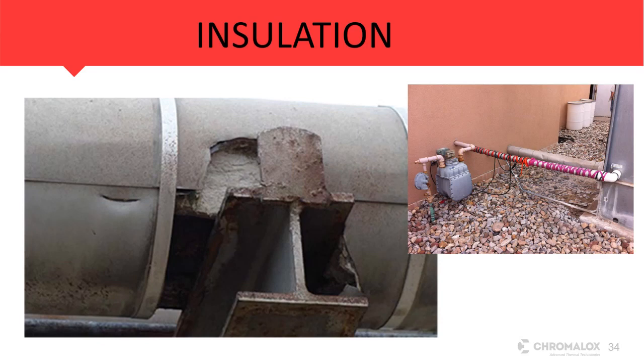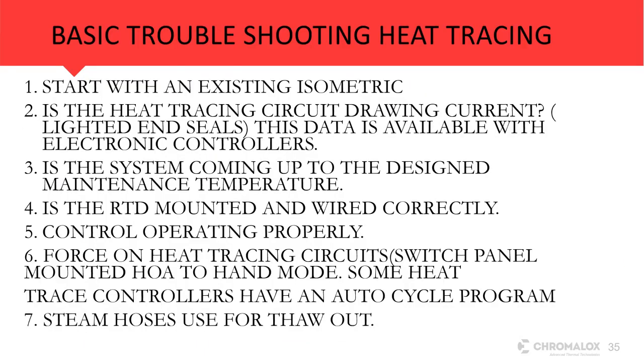So just keep in mind, insulation is a big part of a heat tracing system. The majority of the time, when we go to look at a troubled installation, 90% of the time we find issues with insulation. So make sure you go back and get the insulation back intact like it really needs to be.